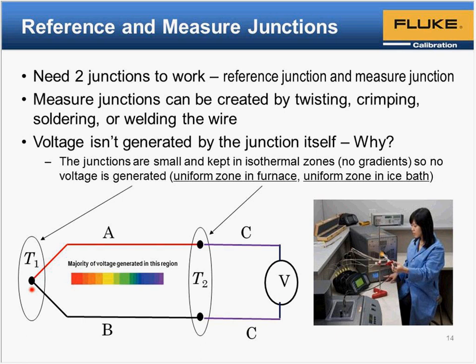And as the wire leaves the furnace, you're creating a zone of wire. The coldest region of the wire is where it leaves the furnace and is in the room temperature environment. If you have set the furnace at high enough temperatures that the wire is vaporizing, or certain components of the wire are vaporizing, they will move along the wire until they reach a point where the wire is cool enough that they can recollect. So it's interesting that the region in the furnace where you are generating voltage is also the region where there's potential for things to start happening to the wire. So anyway, some interesting things about thermocouples in that sense.